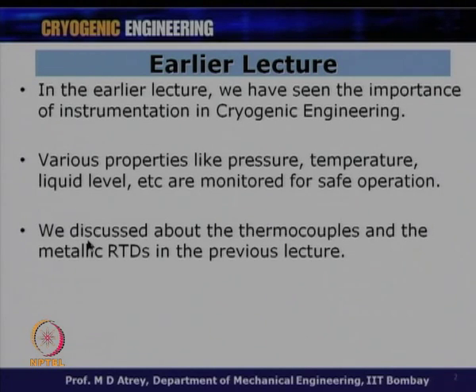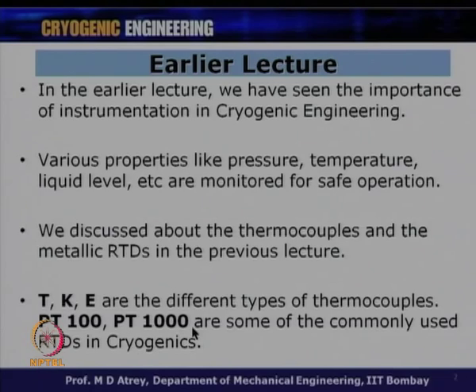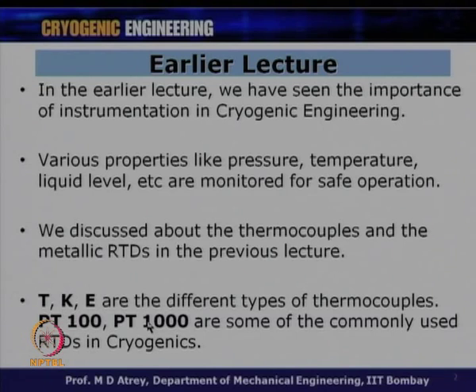We started with temperature measurement and are still continuing with it. We discussed thermocouples and metallic RTD resistance temperature sensors in the previous lecture. T type, K type, and E type are the different types of thermocouples normally used. We also talked about platinum RTDs — PT100 and PT1000 — where 100 and 1000 are the resistances of the sensor at 0 degrees centigrade.